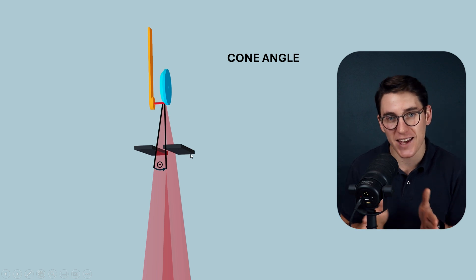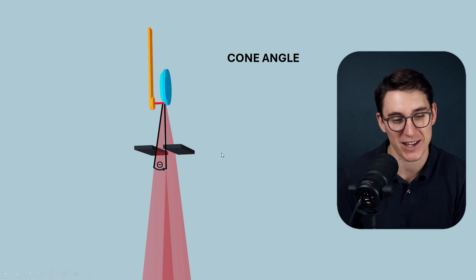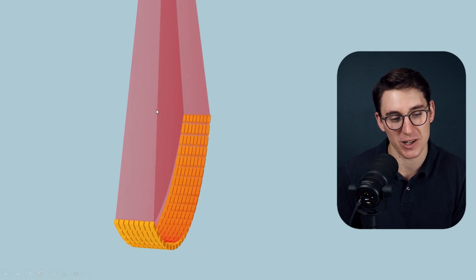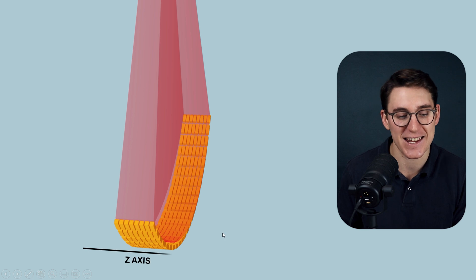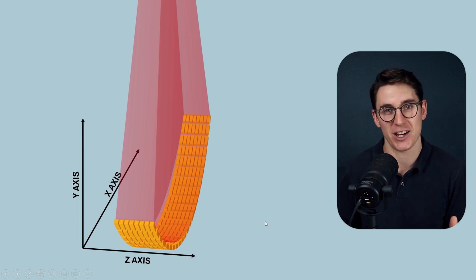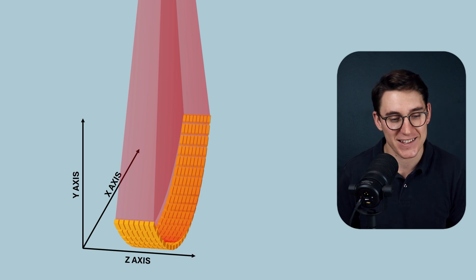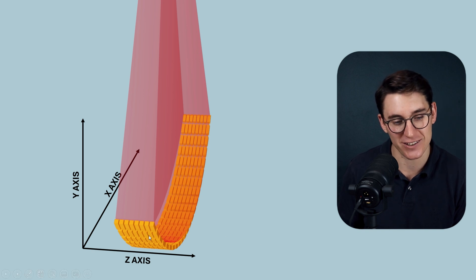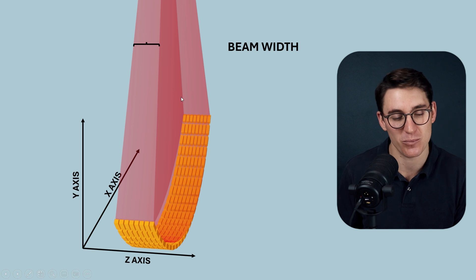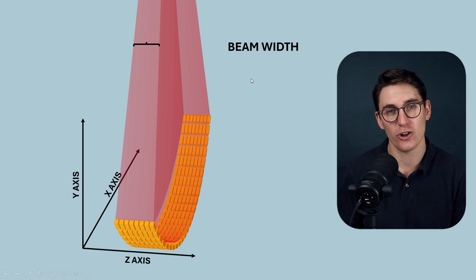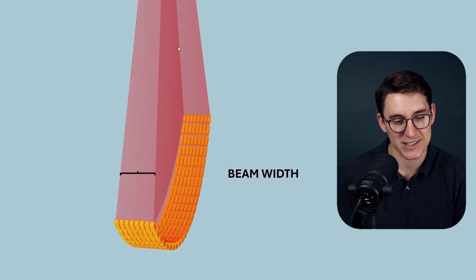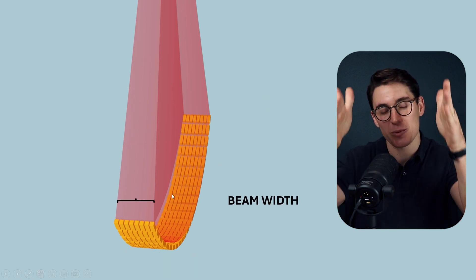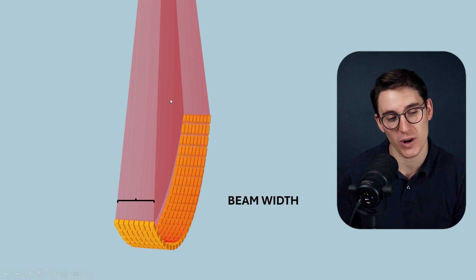So what we're dealing with is fan beam and cone beam geometry — the x-ray beam fanning out in both the x-y plane and the z-plane. This cone angle creates a beam heading out towards our detectors that has some width, covering data along the z-axis of our patient. The z-axis is the longitudinal plane as the patient moves through the CT scanner. Notice how the beam width gets wider as we extend out towards the detectors. The further away from the source in cone beam geometry, the wider the beam is going to be.